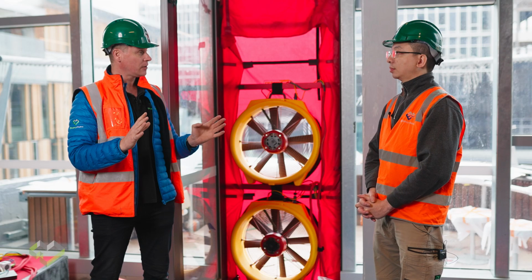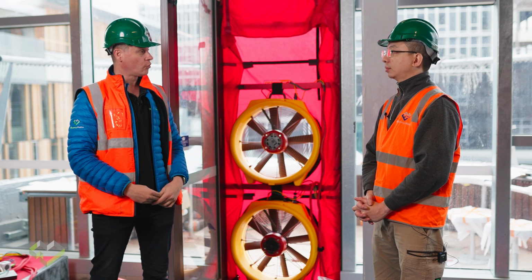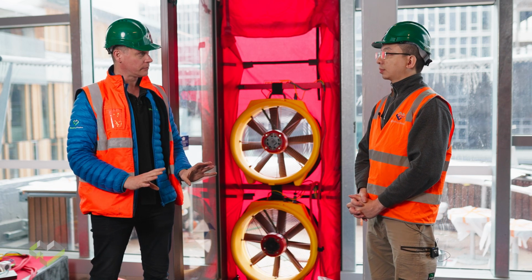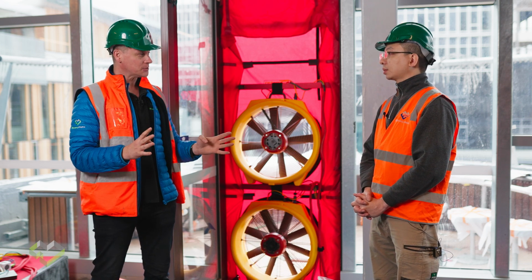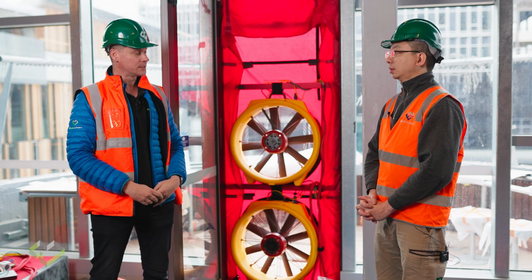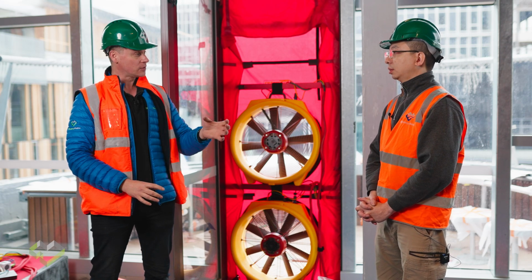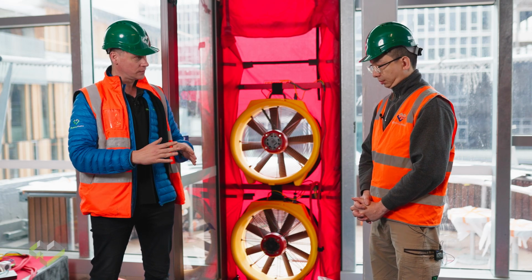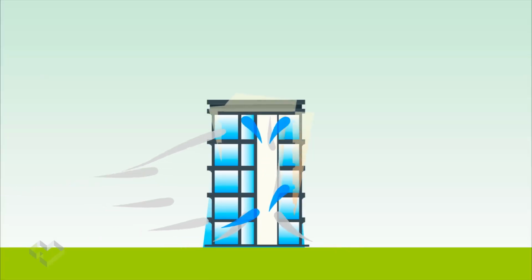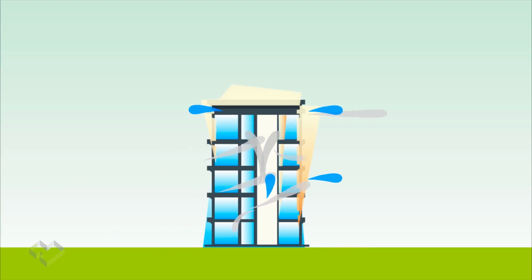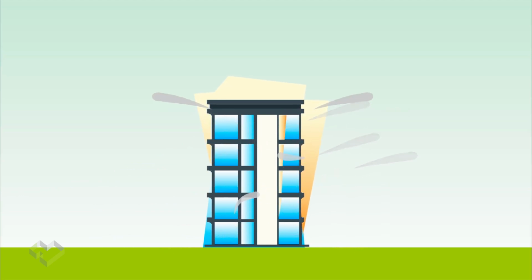Currently, the GBCA or Green Star have a requirement for testing a building to a permeability rate of 20, which is 20 metres cubed per metre square at 50 pascals. In a lot of circumstances, it's very difficult to test a building to that leakage rate because of the interconnectivity of the building to these openings that might be to the outside. What's the easiest way to get cheaper testing and easier tests on these buildings?